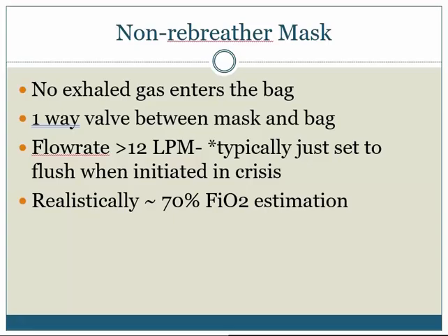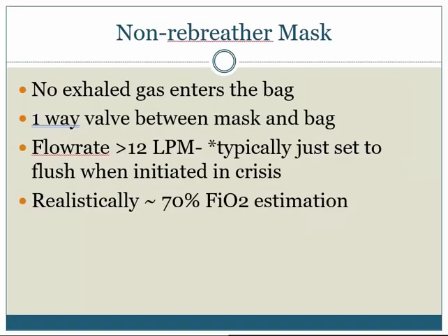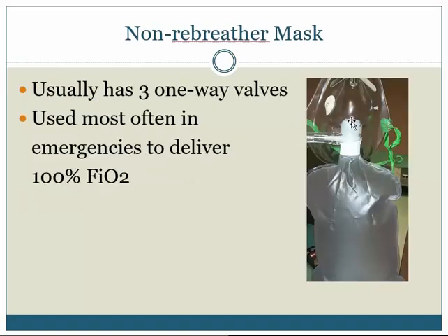Now look at all your faces. We all have different shapes and sizes of faces, so it's never going to seal perfectly on any one person's face. There are three one-way valves, one here and here and here, so that the patient isn't supposed to be breathing in any room air. The one here prevents the patient's exhalation from entering into the reservoir bag. The reservoir bag is entirely filled from the oxygen source.